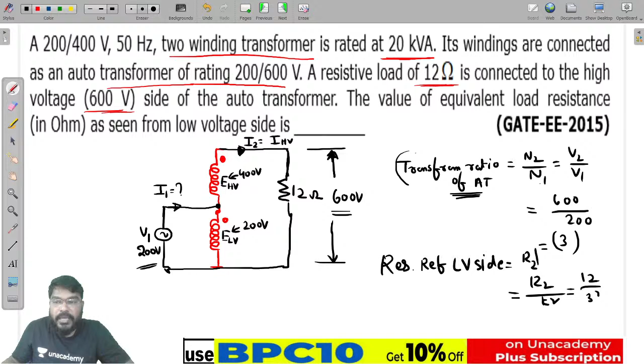Now after transferring this resistance referred to the LV side, that is R2 dash, equal to R2 by K square. Don't confuse this with the turns ratio K value - here we're calculating as in a two-winding transformer with transformation ratio N2 by N1, turns ratio A is N1 by N2. So R2 is 12, K square is 3 square, equal to 12 by 9. So that's the answer.